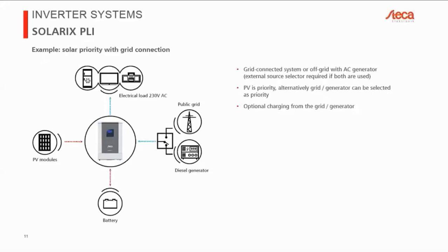And then we can mix the two, of course, which is, I think, the most typical scenario, where, again, we have the AC loads on the AC output. We have PV modules this time on the PV input. Of course, we have a battery. As I mentioned before, all of our inverters require a battery. And then finally, we have a diesel generator or a public grid on the AC input side.